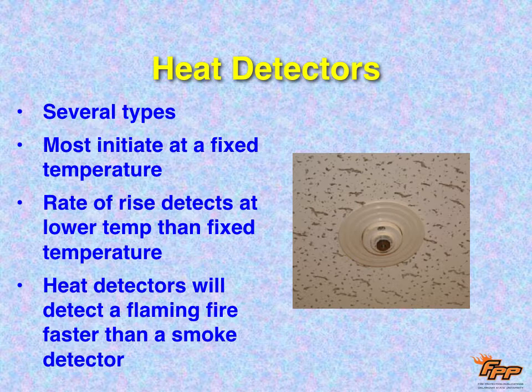The first is heat detectors. They initiate at a fixed temperature or at a rate of rise. So the fixed temperature ones would, at let's say 350 degrees, go off. The rate of rise ones are going to notice a rise of temperature from a lower temp to a fixed temperature in a certain amount of time. So if we go from 250 to 350 in a certain amount of time, it's going to initiate the alarm. So heat detectors will detect a flaming fire faster than a smoke detector, but they cost more, and there are other issues with heat detectors.